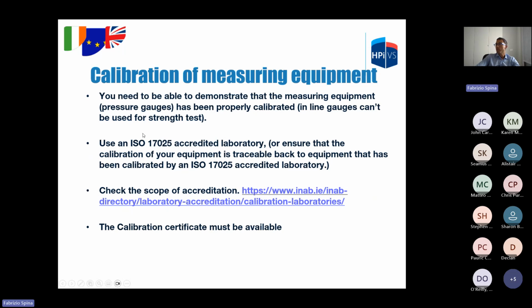When performing the pressure test, it is necessary to use measuring equipment that fulfills some requirements. The pressure gauge must be properly calibrated. An ISO 17025 accredited laboratory must be used for the calibration of the gauge, or the gauge must be calibrated based on another gauge calibrated by the accredited laboratory. The calibration certificate must be available on site for the inspector to check. If you are in doubt whether a laboratory is accredited or not, you can check on the INAB website.